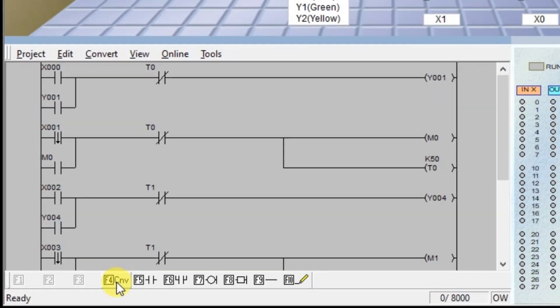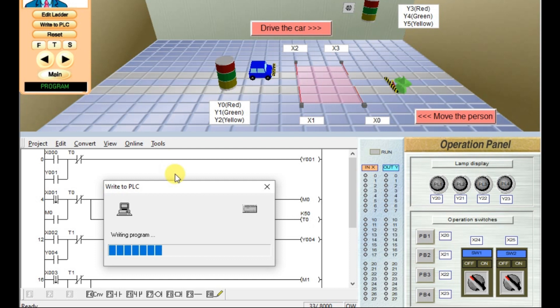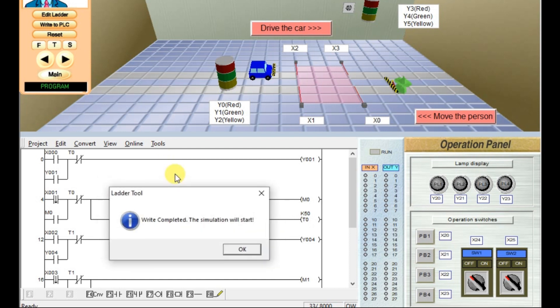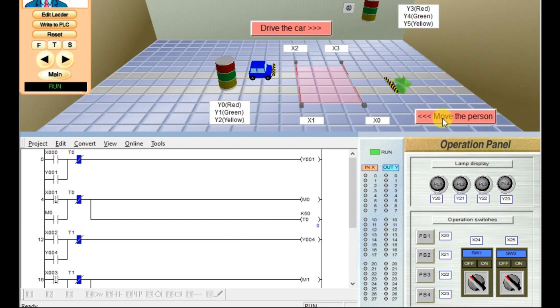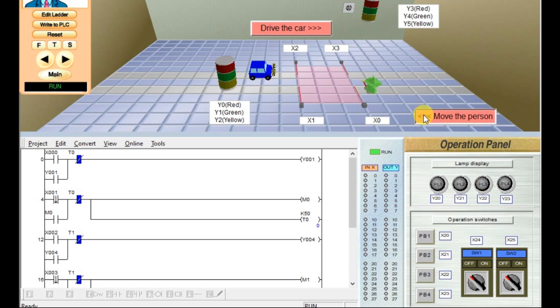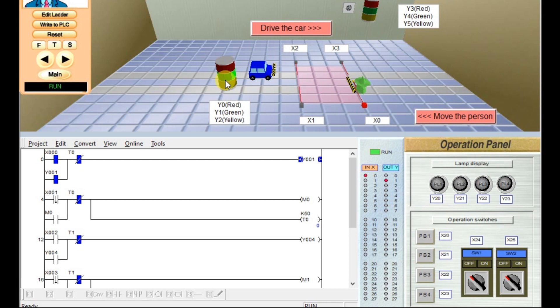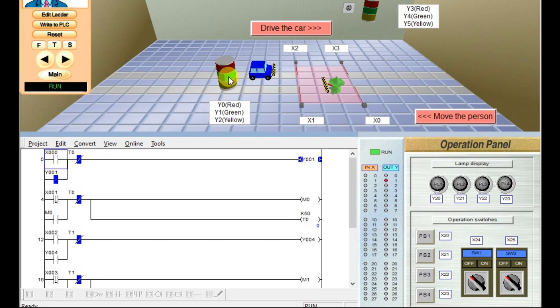We will test it using simulation. First convert it and then write to PLC — it will download to the PLC. If I click this button, it moves the person. I will do this step by step. Now the person is before the entry sensor. This entry sensor is on; X0 is on, and the green lamp is also on. If you see in the logic, X0 is on, Y1 is also on — Y1 is nothing but the green lamp. Now I will move this person a little bit forward. X0 is off, but the green lamp is on because with the help of the latch, the green lamp is continuously on even though the input is off.